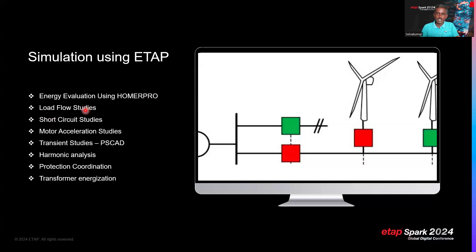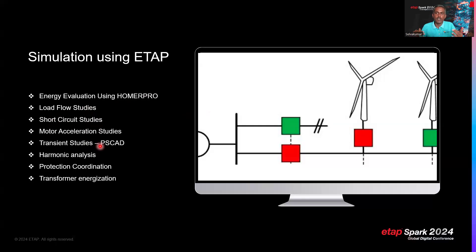Beyond energy evaluation, the technical feasibility of the solutions must also be validated — meaning how the system technically functions under all conditions. This requires load flow studies, short circuit studies, motor acceleration studies, and transient studies. To capture the dynamic behavior of the wind turbine generator as well as the battery energy storage system, ETAP plus PSCAD co-simulation provides optimal results.